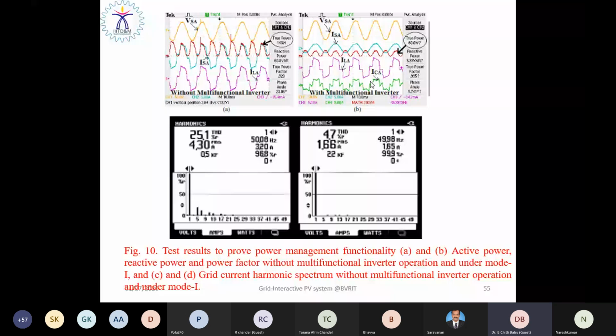The THD of the grid current without any controller was about 25.1%. Now with the controller, it has been reduced to 4.7%. Right, and moreover, the power factor becomes unity, and the frequency is almost 50 hertz. And this is without a multifunctional inverter.